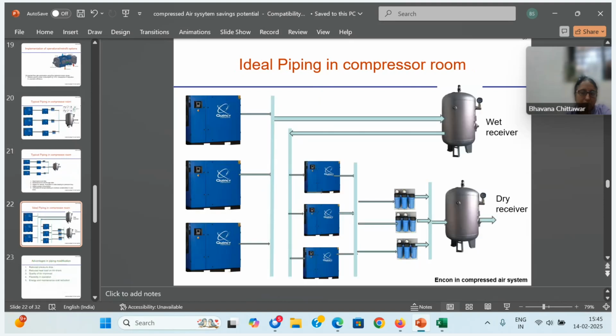So how should it be? There should always be two receivers: one wet receiver and one dry receiver. All compressors should be connected to a header, and from the header to the wet receiver, and again one more header to the individual dryers, and then filters in parallel, not in series, and to the dry receiver. What are the advantages here? You can choose any compressor, any dryer, any filter.